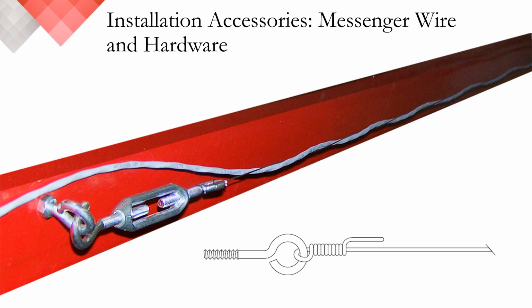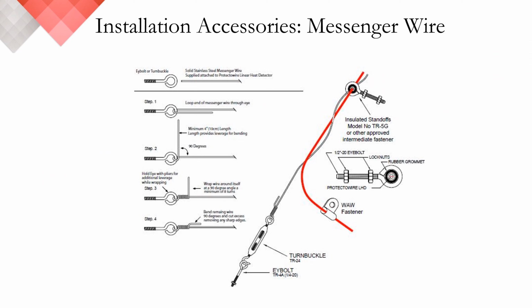However, spacing should never exceed 50 feet or 15 meters, as you may experience some excessive sag. Outdoor messenger wire installations present an additional challenge due to environmental factors such as snow and ice buildup or wind. Increased detector support must be provided by using additional supports with closer spacing. And here's a great illustration of the components required and the method used to properly install your messenger detector. A copy of these guidelines is available through our website.